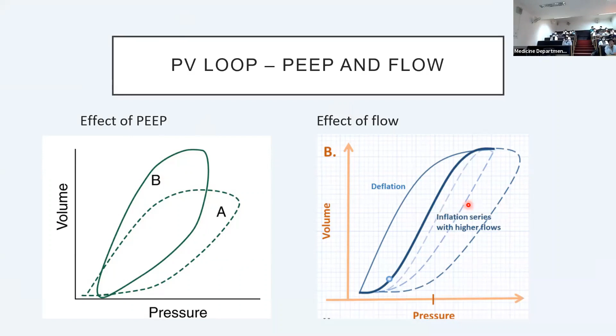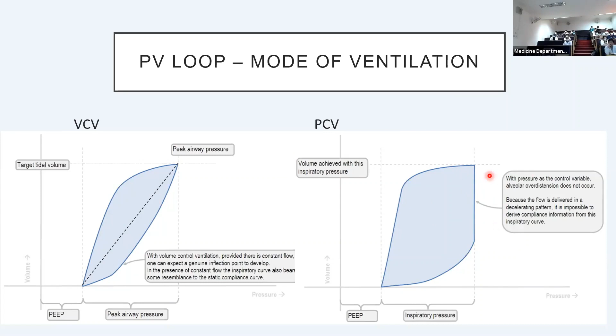That's the effect of PEEP. And as we said, if you increase the flow, you're going to increase the airway resistance that is visualized, and the loop will again widen. The PV loop also changes based on the mode of ventilation. VCV is what we've been talking about, and you can calculate the compliance only in VCV with a constant flow. Otherwise, in PCV, it takes on a more box-shaped character because the pressure is not allowed to increase in PCV.